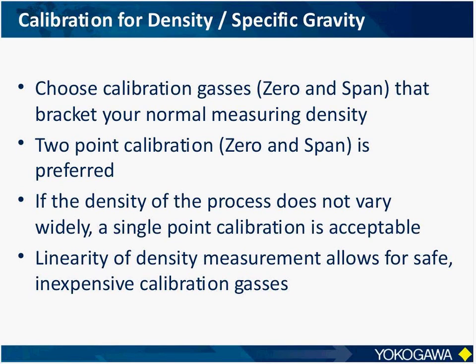For example, if your process has a density that's very close to, say, acetylene, most people don't want to have acetylene sitting around for calibration. It's flammable, it's dangerous, so you can choose something that has a close density to that value, but is much safer, something like nitrogen, something like helium.